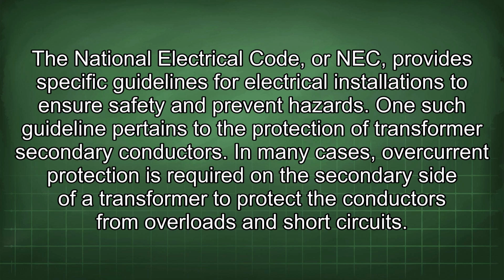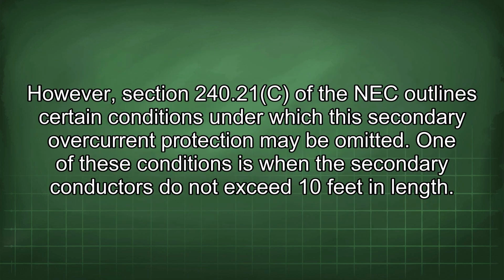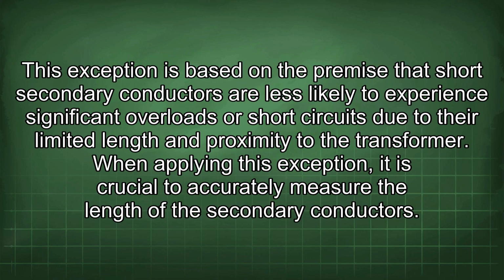The National Electrical Code, or NEC, provides specific guidelines for electrical installations to ensure safety and prevent hazards. One such guideline pertains to the protection of transformer secondary conductors. In many cases, overcurrent protection is required on the secondary side of a transformer to protect the conductors from overloads and short circuits. However, section 240.21(c) of the NEC outlines certain conditions under which the secondary overcurrent protection may be omitted. One of these conditions is when the secondary conductors do not exceed 10 feet in length. This exception is based on the premise that short secondary conductors are less likely to experience significant overloads or short circuits due to their limited length and proximity to the transformer.